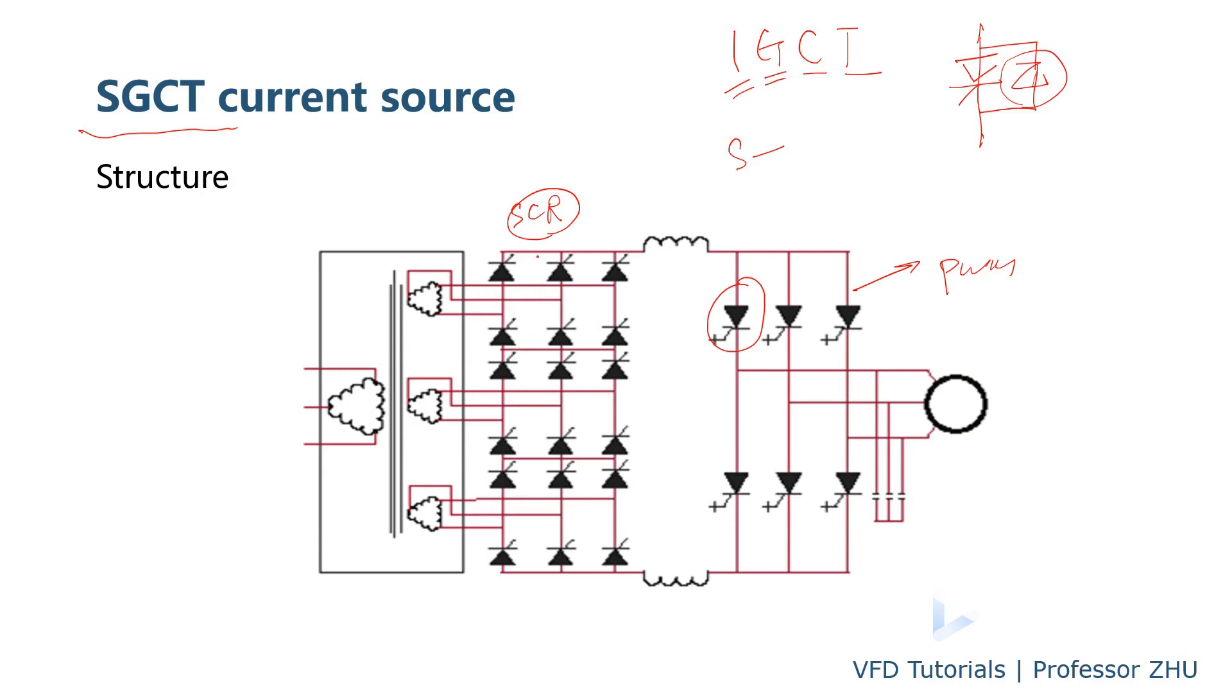For SCR you can have this topology like 18-pulse. So you have three sets of rectifier. And each secondary you have a 20 degree phase shift. And you have an 18-pulse rectifier.